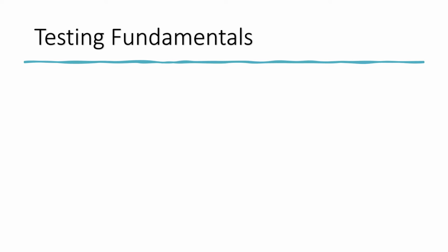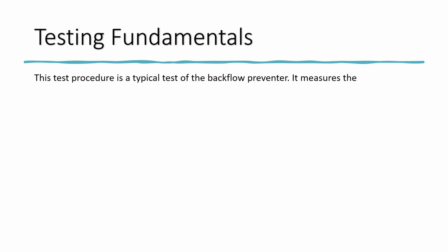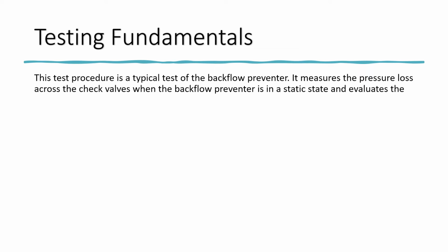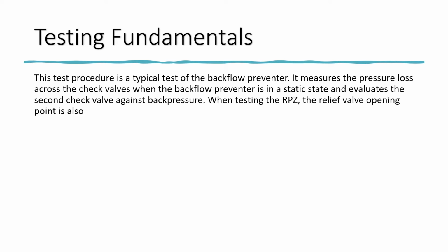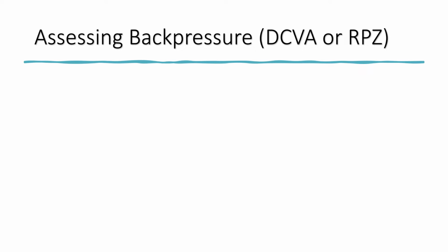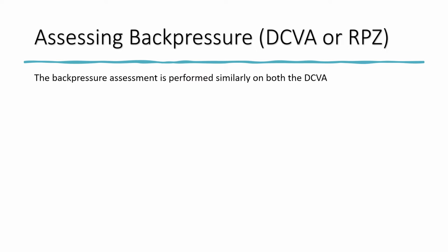Testing fundamentals. This test procedure is a typical test of the backflow preventer. It measures the pressure loss across the check valves, when the backflow preventer is in a static state, and evaluates the second check valve against back pressure. When testing the RPZ, the relief valve opening point is also measured. Assessing back pressure, DCVA or RPZ. The back pressure assessment is performed similarly on both the DCVA and RPZ.